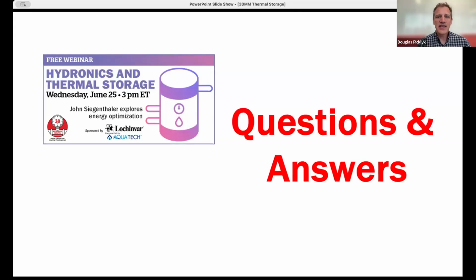Someone asked, and again, I think we're referring back to that first image, why is there a differential pressure bypass? Wouldn't it be very worth it to put a smart circulator instead? Okay, now I'm going to tell you to read the article in June HPAC, and it explains why it's there, but I'll give you a quick summary. It's there because when the heat pump first turns on, the circulator turns on first and will run for 2 to 3 minutes before the compressor starts.